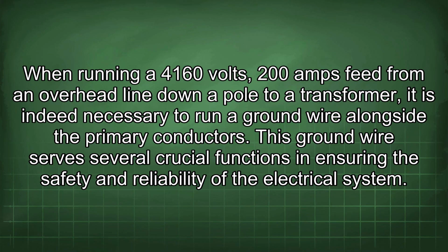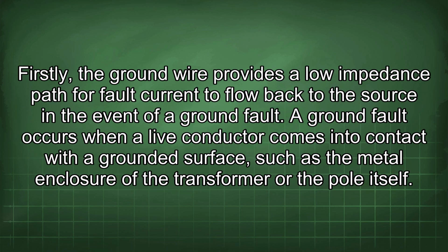When running a 4160 volts 200 amps feed from an overhead line down a pole to a transformer, it is indeed necessary to run a ground wire alongside the primary conductors. This ground wire serves several crucial functions in ensuring the safety and reliability of the electrical system. Firstly, the ground wire provides a low impedance path for fault current to flow back to the source in the event of a ground fault.